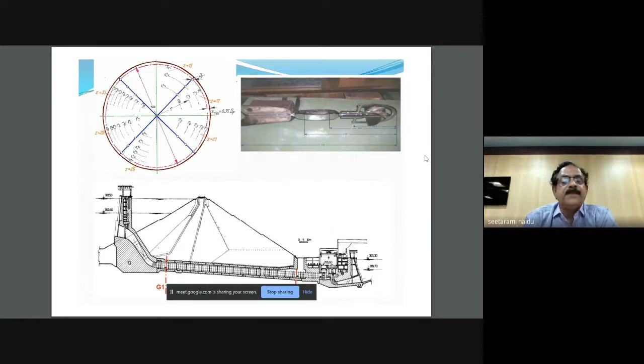We have to shut the plant, dewater the penstock, weld or fasten these cross arms, fit the current meters, extend the wires and connect them to the plotter, where we get a pulse train. With the use of a planimeter and the velocity-area method, we can calculate discharge. But it needs almost 1 week of shutdown for this measurement. So nowadays it is discouraged because of big demand, and in its place the ultrasonic flow meter has taken over, and it can be done without disturbing the system.